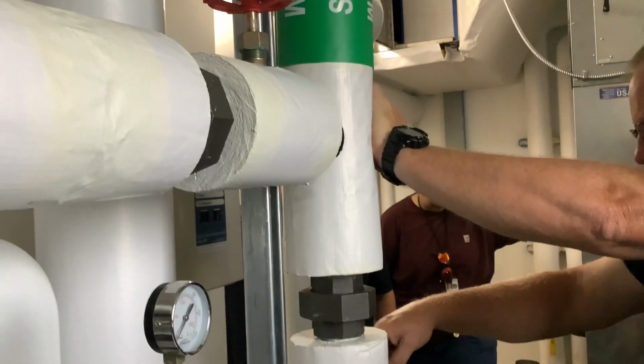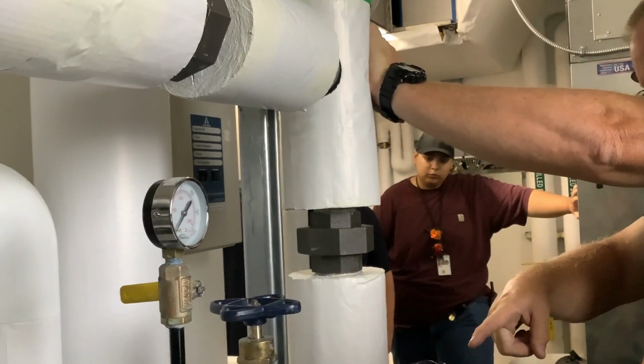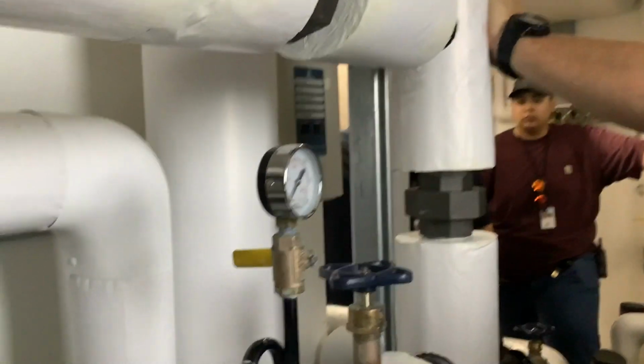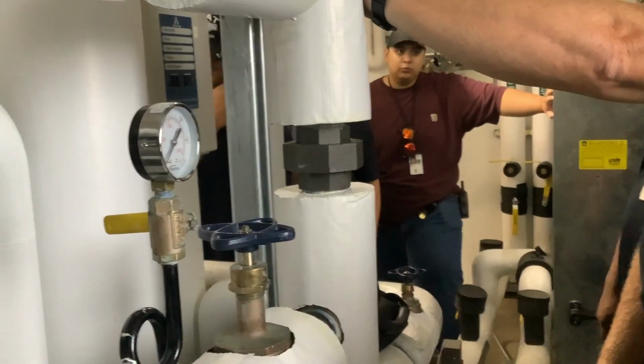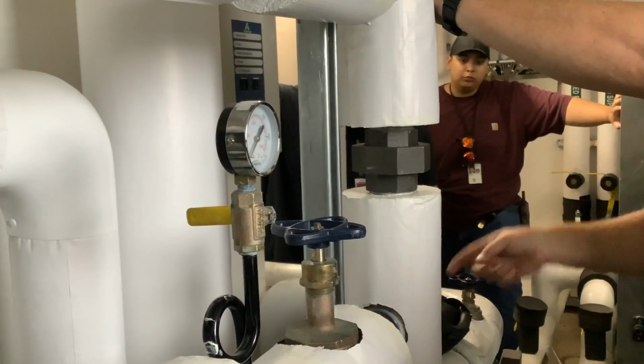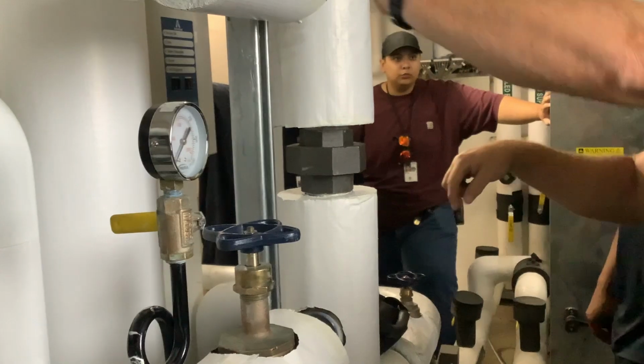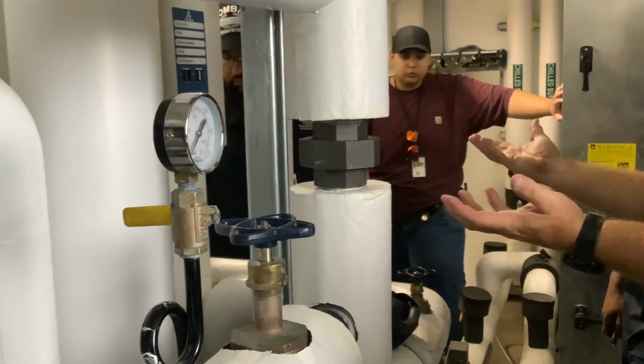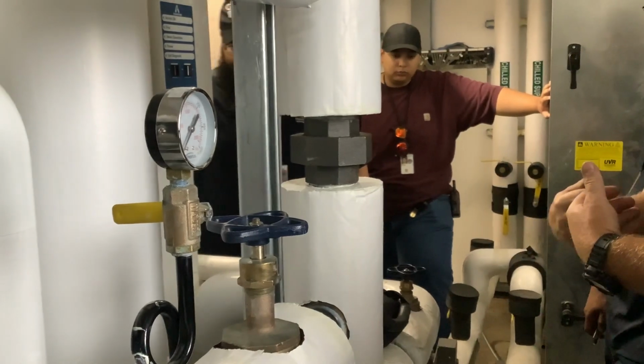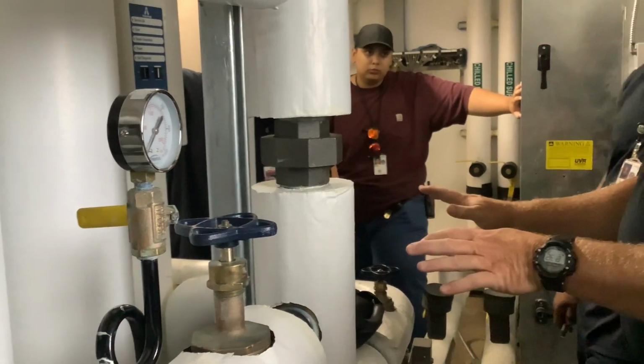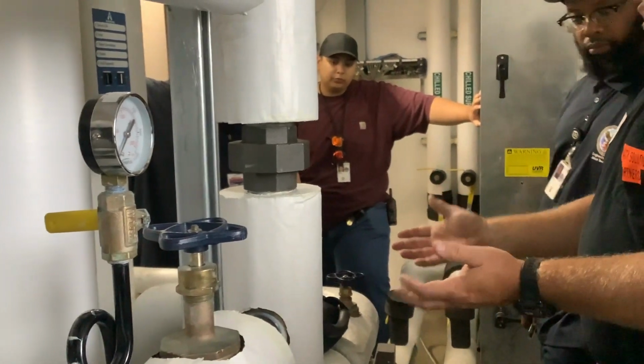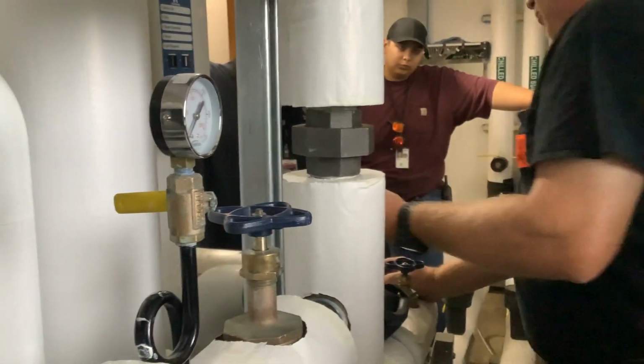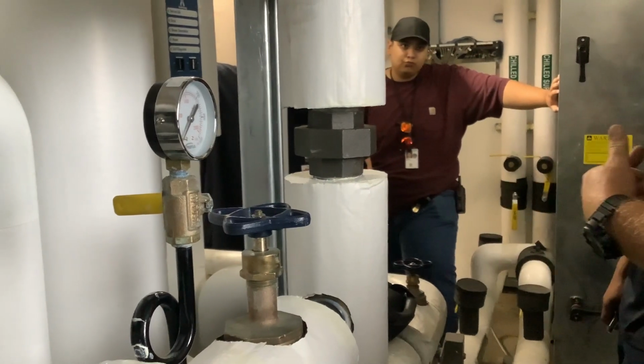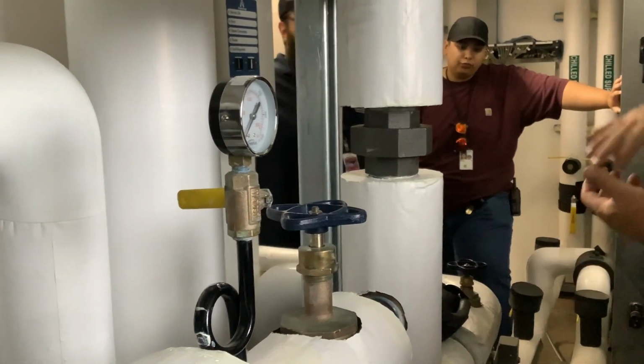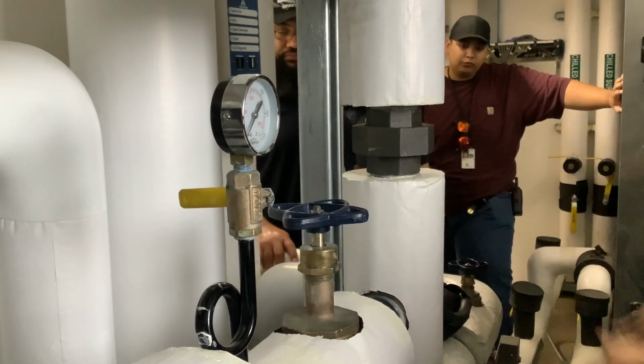That top needs to be looked at at least once a year. You have to pop the top and pop the unions and look at this, because obviously you've got them everywhere else, and you know what forms in there. You get a bunch of scale and stuff in there. Now, whether you need to do anything with it the first year, possibly not, depending on your water quality. If your water quality is good, you normally won't have to deal with it. But if you do, you might have to clean the scale out of there, because we don't want the water elements covered with scale, since otherwise it won't work very well.